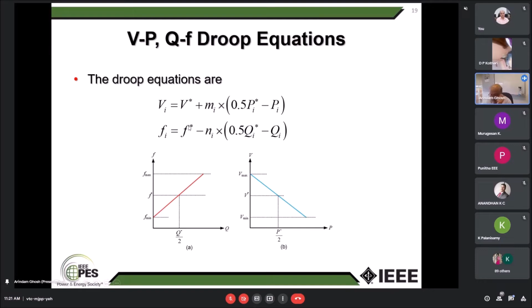Now if you look at this performance here, you will see the reactive power is shared in the ratio of 4 to 1, as a result of which your frequency is now converged for the two DGs. But the main problem here is your real power is not shared properly. Now you say that's not good, obviously my generators should share power according to their ratings. Now if I am not able to do that, what good is it? Obviously we have to modify this method, or do alternate solutions for this.